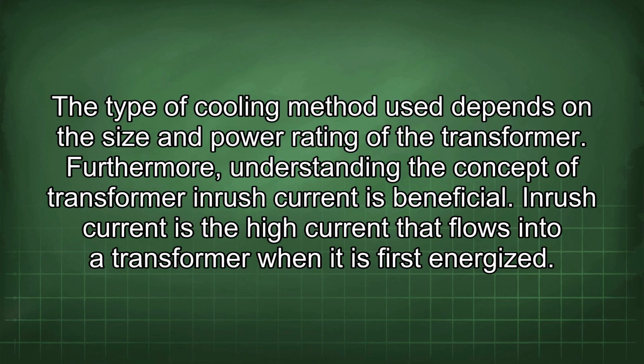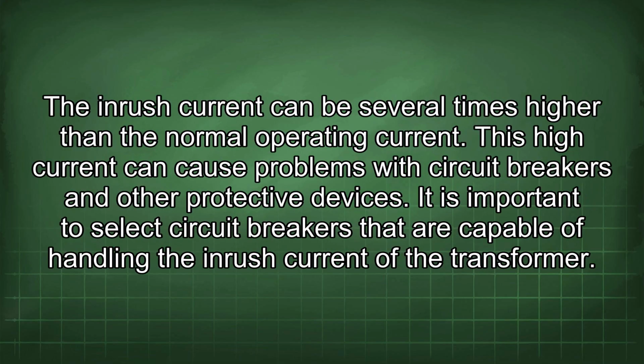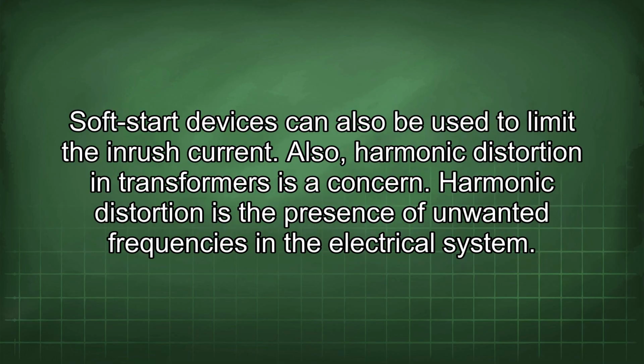Furthermore, understanding the concept of transformer inrush current is beneficial. Inrush current is the high current that flows into a transformer when it is first energized. The inrush current can be several times higher than the normal operating current. This high current can cause problems with circuit breakers and other protective devices. It is important to select circuit breakers that are capable of handling the inrush current of the transformer. Soft start devices can also be used to limit the inrush current.